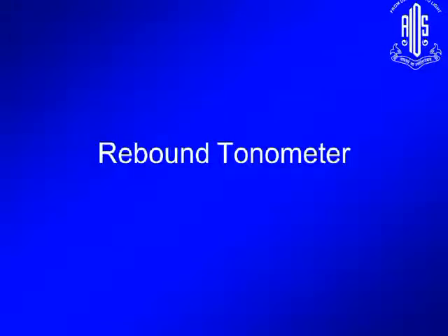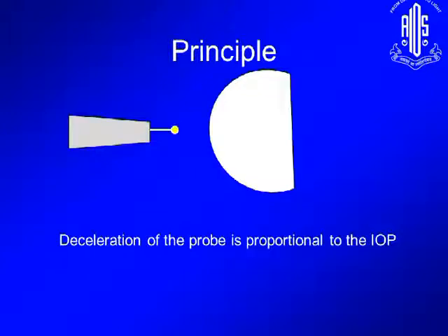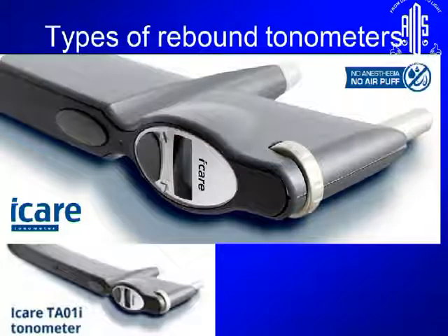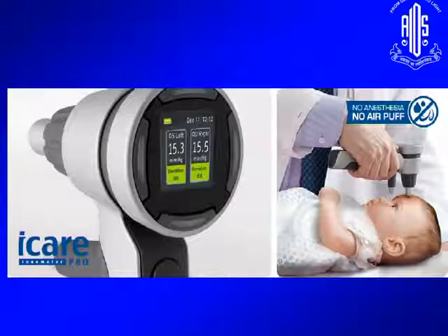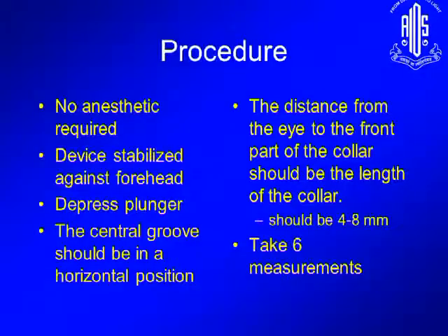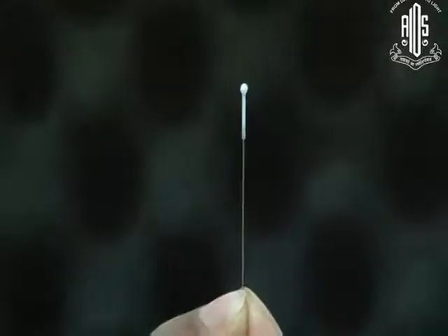We next move to the Rebound tonometer, and the principle is pretty similar. It's in a way unique. You have this probe which floats in this tip, and it bounces against the cornea, and the slowing of the probe tells you how hard the eye is, and therefore from that you can derive what the intraocular pressure is. There are three versions. This is the first version which came out. This version lets you do it in a vertical position, and this version is for self-tonometry, which patients can use. No anesthetic is required, and I will just show you how that is done.